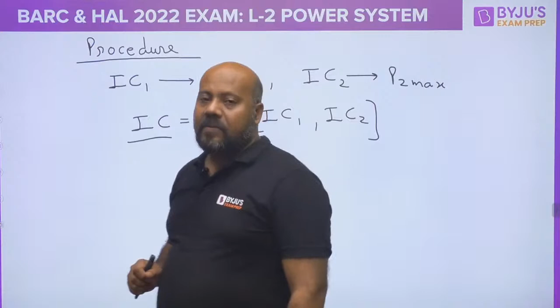Now from this diagram, you can very easily understand that when you are talking about PD max, maximum power to be supplied to the load, you have to go for the minimum of these two incremental costs, because that will be available for both the generators. So when asking about PD max, you go for the minimum value of the incremental cost.